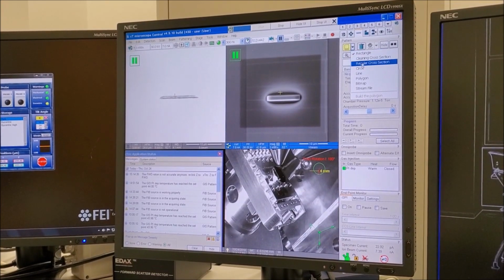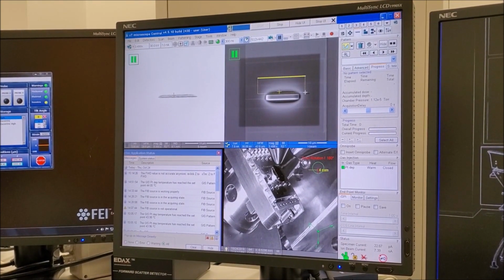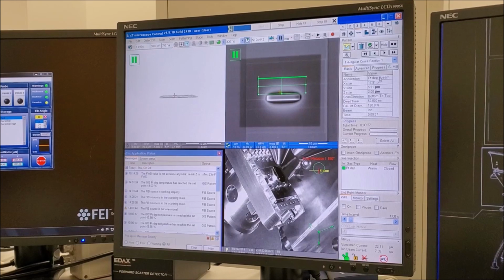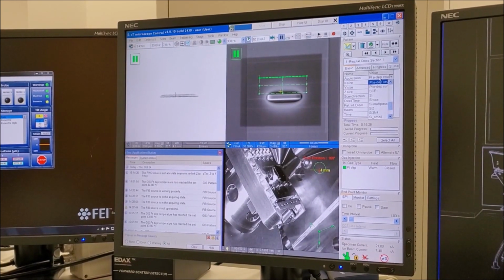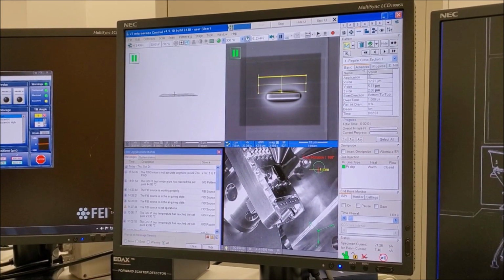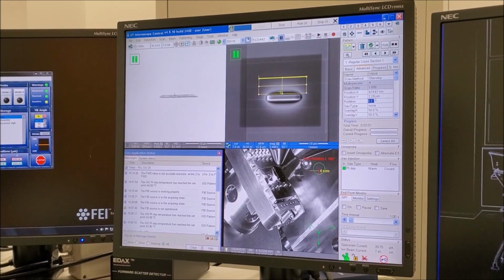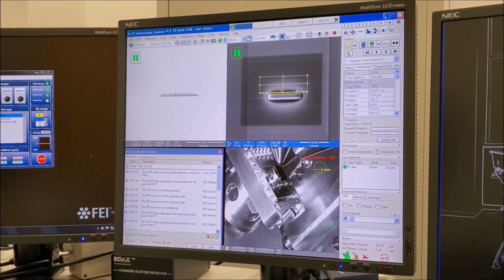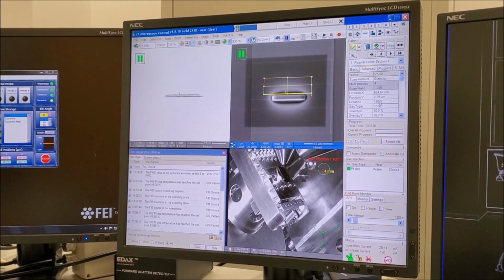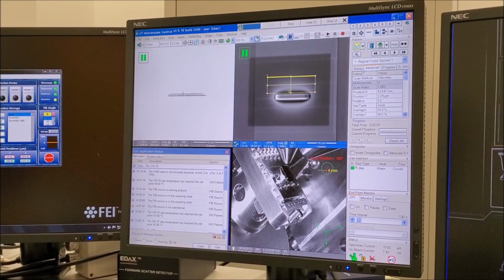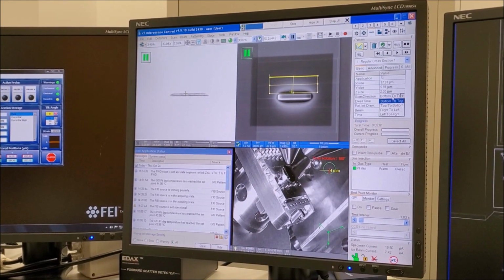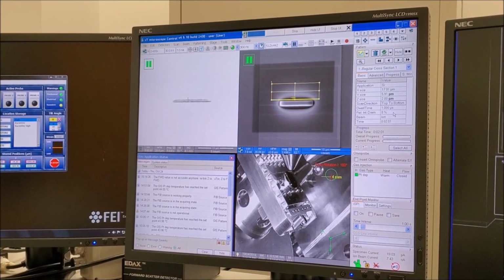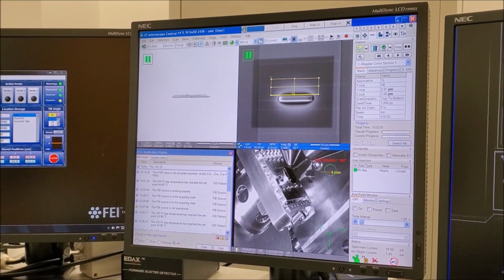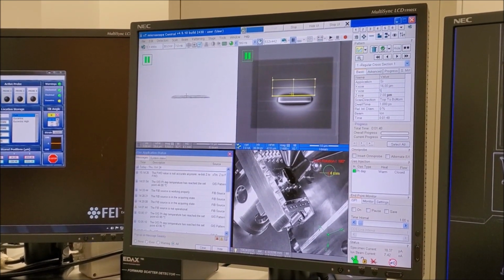In the patterning module, select the regular cross-section pattern and click and drag to draw on the ion beam quad. In the Basic tab, change the application to silicon. Then go to the Advanced tab and set the rotation as needed such that the thick line of the pattern is closest to the platinum strip. Return to the Basic tab and adjust the X, Y, and Z parameters as needed.